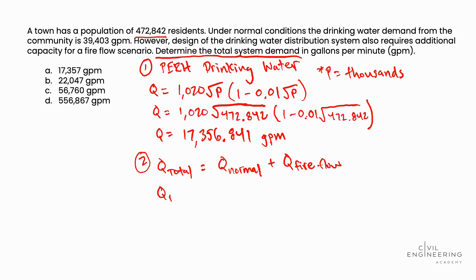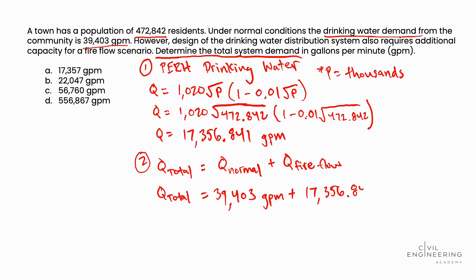To determine the total demand, Q_total equals Q_normal, the normal demand, which we're told in the problem statement is 39,403 gallons per minute, plus the fire flow demand we found in step 1, which was 17,356.841 gallons per minute. Performing the calculation, we determine that the total system demand is equal to 56,759.8 gallons per minute.